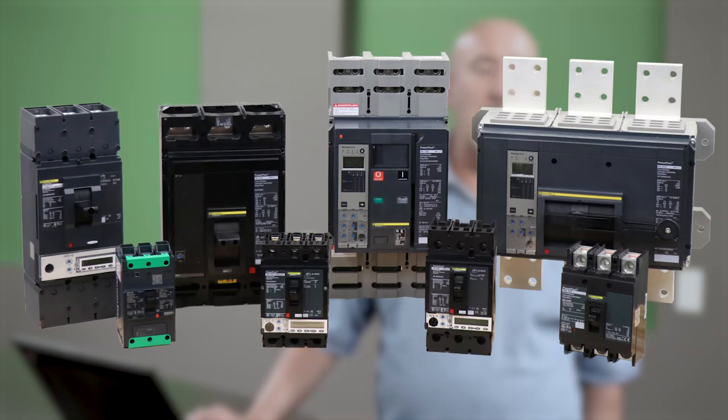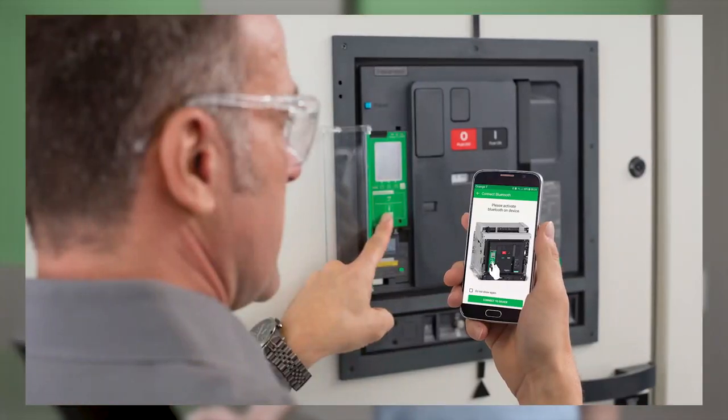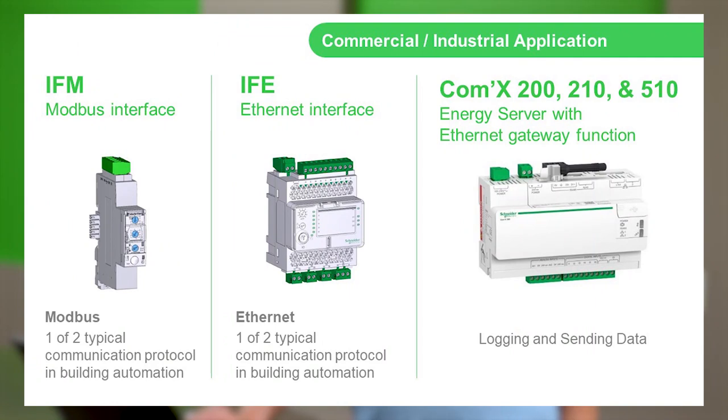Now we move on to commercial and industrial applications. With the WISER application we were talking about miniature QO breakers in a QO load center. Now we're getting into PowerPact breakers and MasterPact breakers that utilize the Micrologic trip units. If the user is on a Modbus connection, the Micrologic trip unit is connected to an IFM, which communicates all of that data over a Modbus connection. The middle device is an IFE, which communicates over an Ethernet interface. And on the far right, you have the Com'X, which is the server that connects all that information to the end-use product — the smartphone, the laptop, etc.